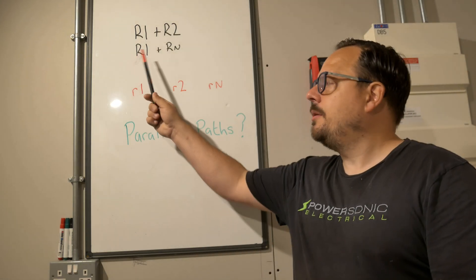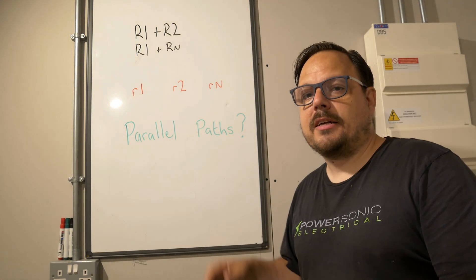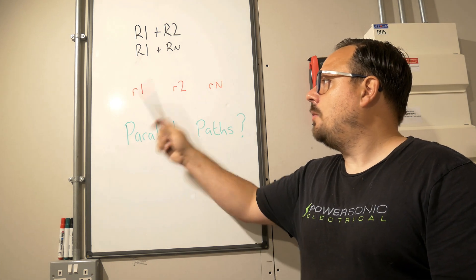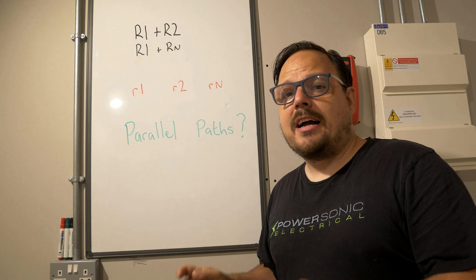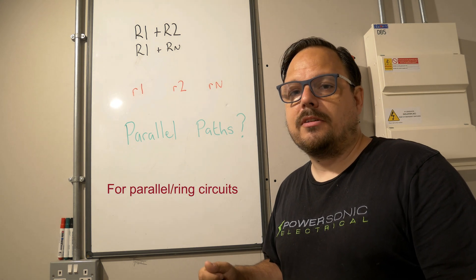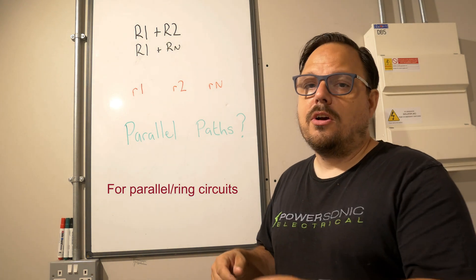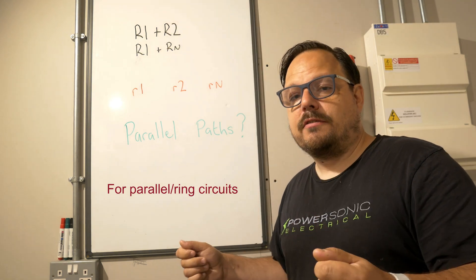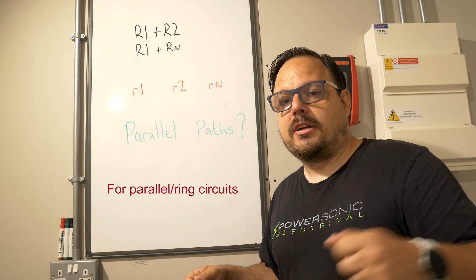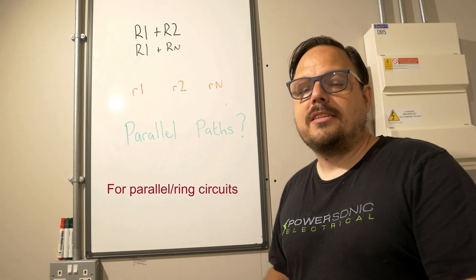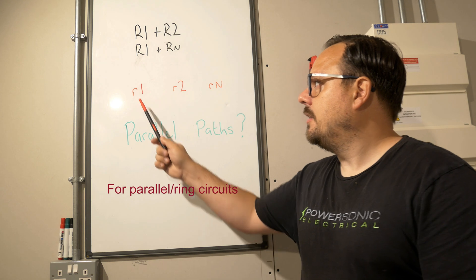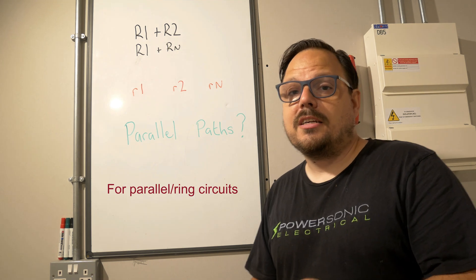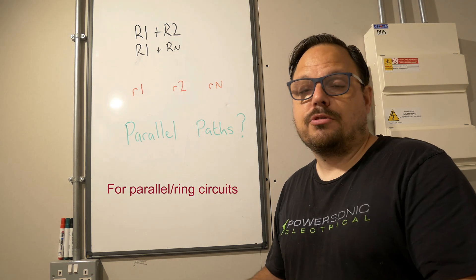We'll start by explaining why we use a capital letter and a non-capital to identify the different measurements. With little R1, little R2, and little Rn, in essence they are end-to-end resistances of a length of cable. That cable can run through a socket circuit, a lighting circuit, or even just be a piece of cable laid across the floor. You would put a crocodile clip onto one end, one on the other, and take a value of resistance: little R1 is your line conductor, little R2 is your CPC, and little Rn is the neutral conductor.